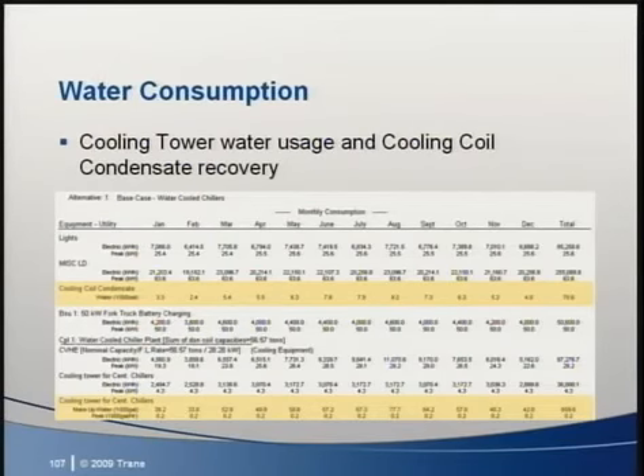The makeup water flow is calculated by entering the amount of water evaporated by the cooling tower in the heat rejection library. So for example, if the heat rejection equipment evaporates 3.5 gallons per ton hour, enter 3.5 as the value and gallons per ton hour as the units. However, if "to be calculated" is selected, the value of the makeup water is ignored.